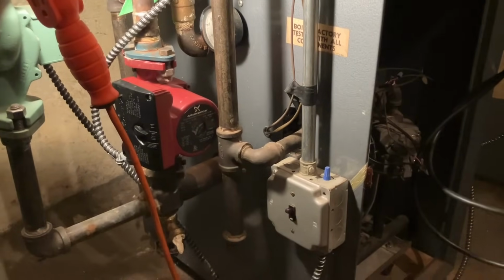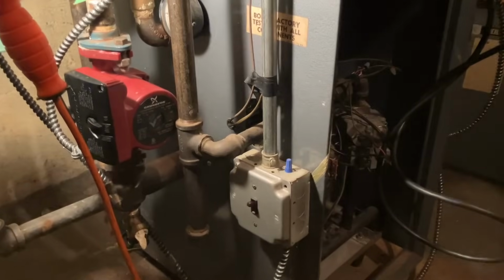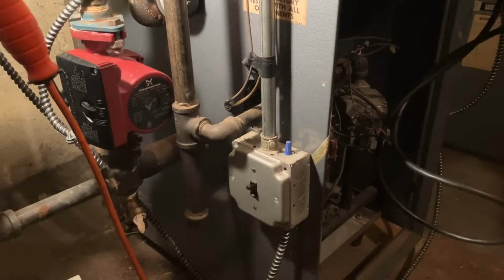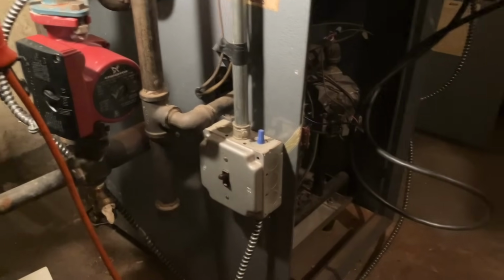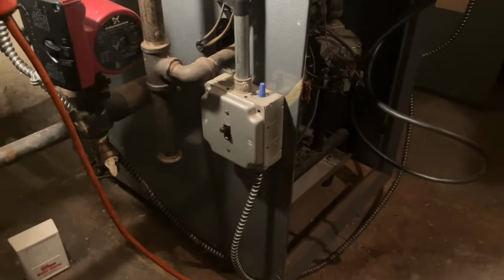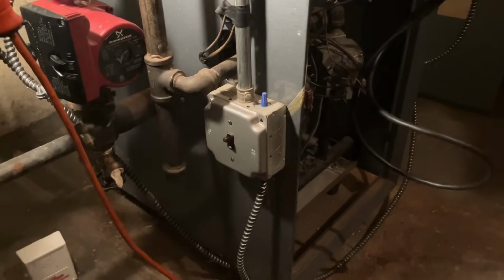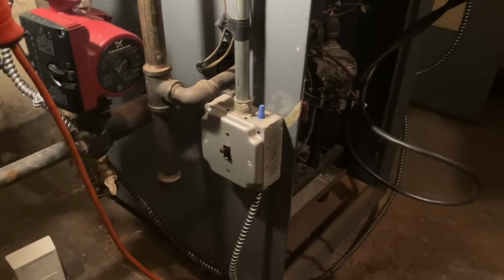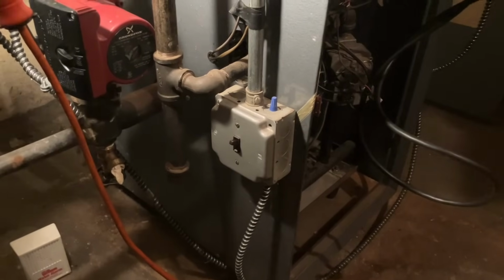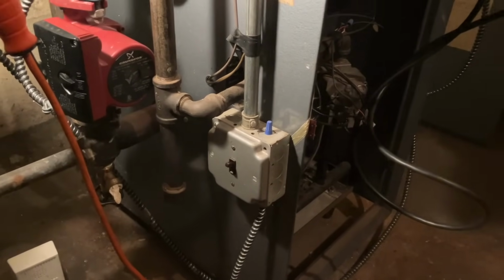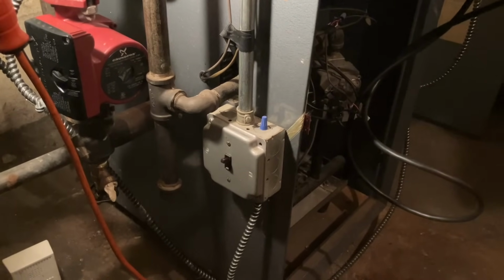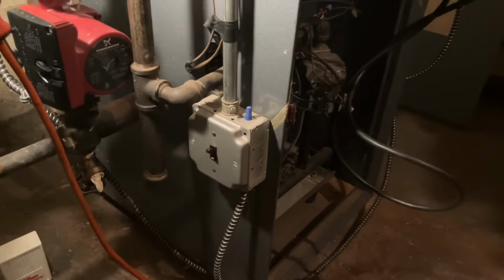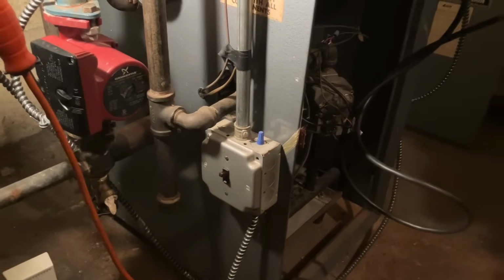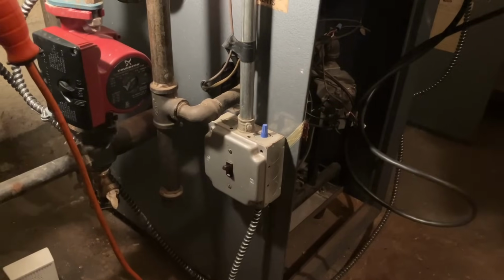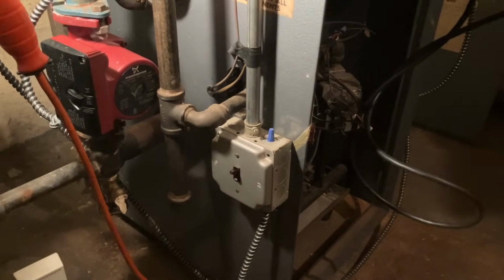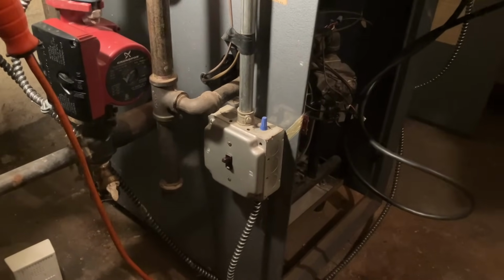So let's say, for example, I have a condensing tankless boiler in my house. I have a mix of roughly 50% radiant heat, which is in-floor tubing, which needs 120 degrees of water to heat the house, and baseboard with convectors, kind of like what you have, which needs on cold days 180 degrees of water. Okay, I have that system year-round set for 145 degrees. My house is also well insulated, but on those cold days when it drops below 30-ish degrees, I've got to jack up that temperature, but I won't dare go above 165 because it defeats the whole purpose of having this tankless boiler, which is condensing in nature, and it thrives at that lower temperature. I might as well put a regular boiler in.